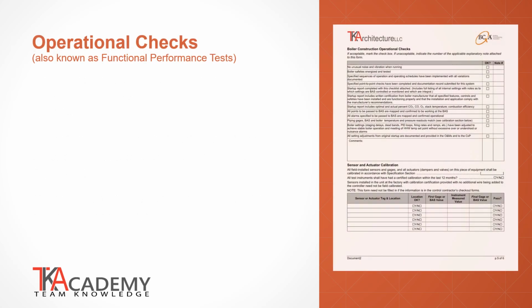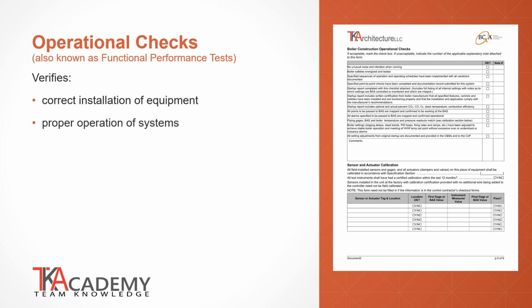After the equipment and systems have been properly installed and gone through initial startup, the commissioning provider will perform the operational checks, which are also known as the functional performance test. Operational checks in building commissioning are tests and inspections conducted to ensure that the building systems and components are installed properly and functioning correctly and efficiently before the building is handed over for operation.